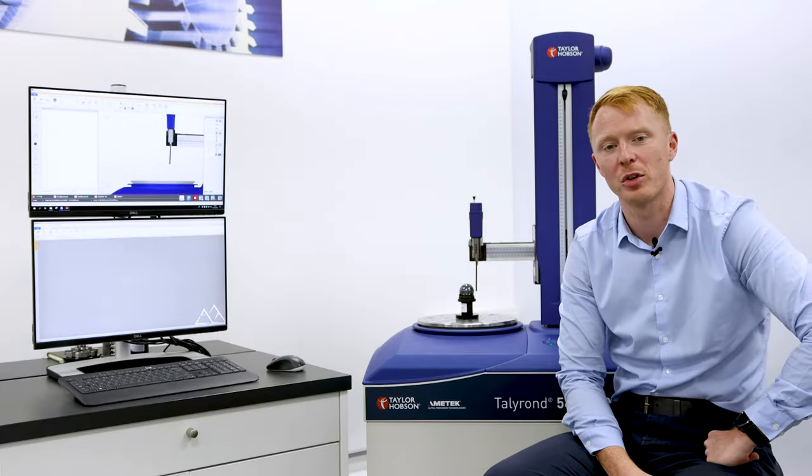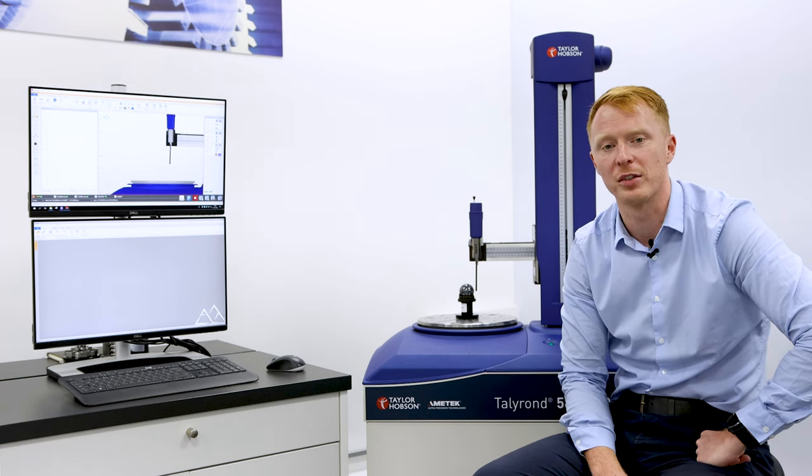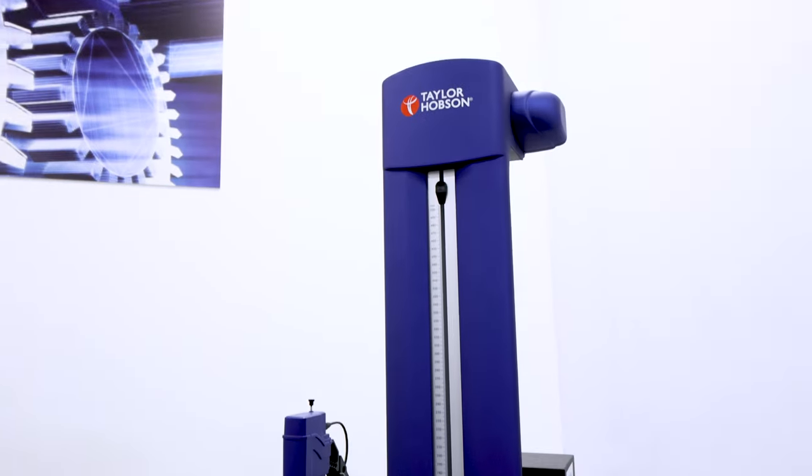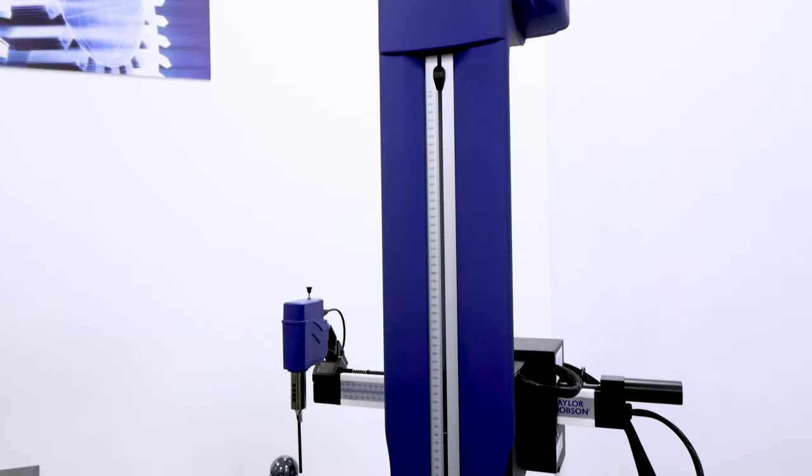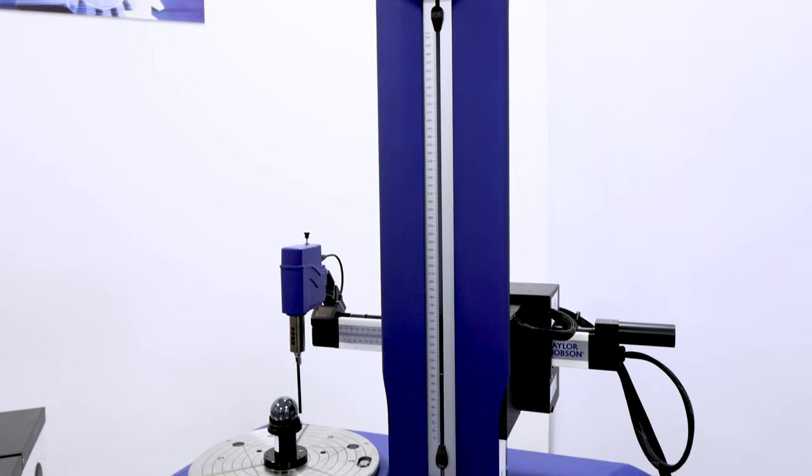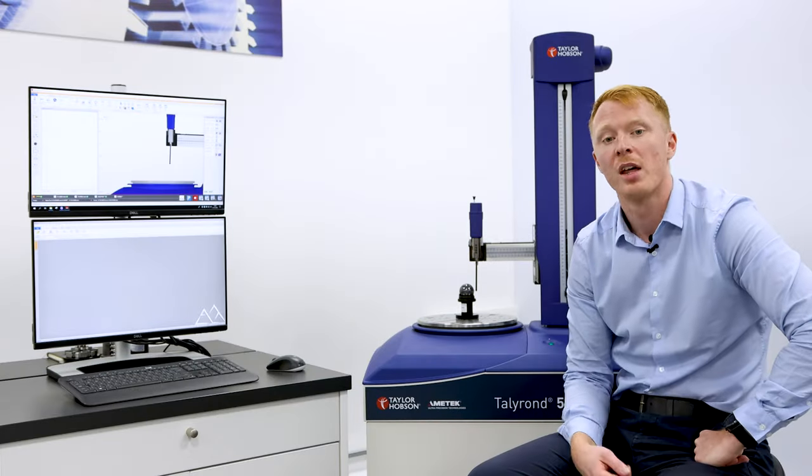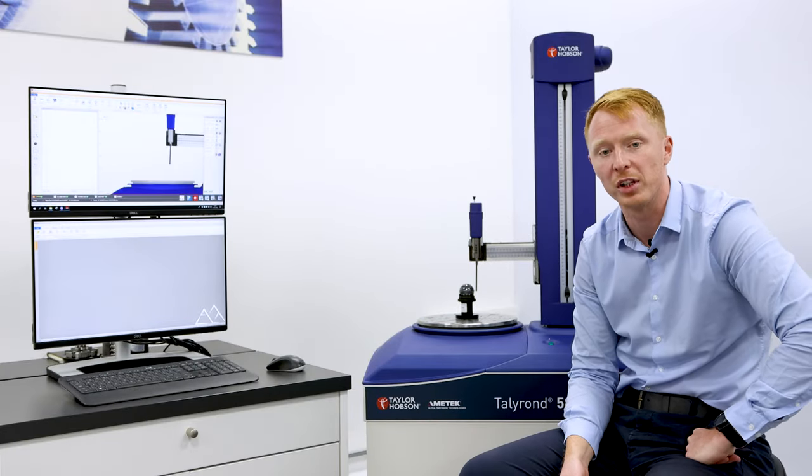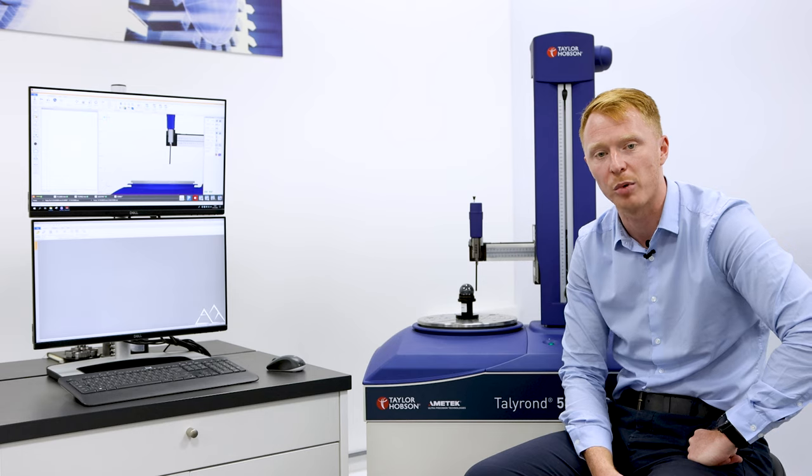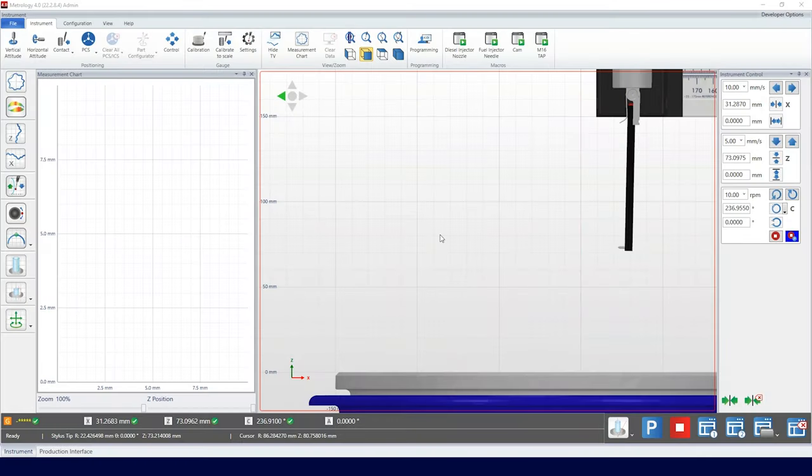A really useful feature in Metrology 4 software is the valid duration for calibration. It's important for some customers to calibrate on a regular interval. This option will prompt the user when the calibration goes out of date.